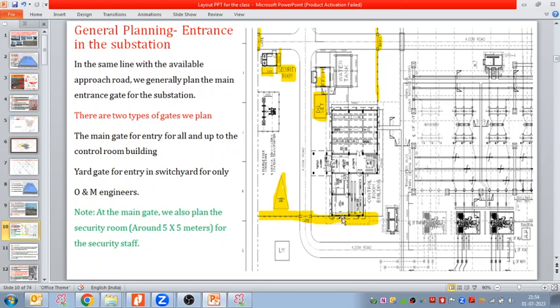One more thing: if this fencing is metallic, we have to do proper earthing of the fencing. We will discuss the earthing of fencing in the earthing module, but I'm mentioning it here since we're discussing fencing. If any fault happens, there could be a chance for the fault current or GPR of this fencing to also become high, so we have to do proper earthing of this fencing as well.